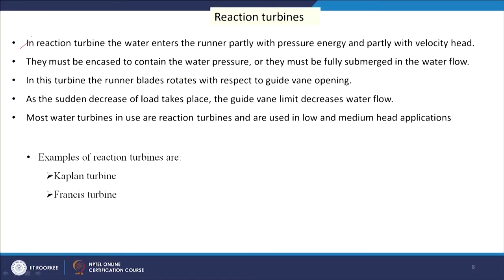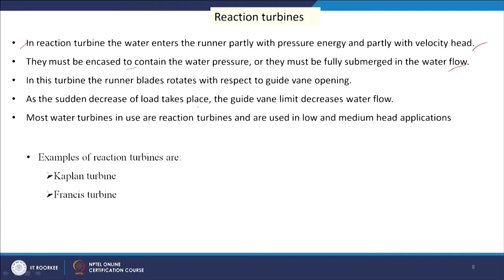In a reaction turbine, unlike an impulse turbine where water passes through nozzles and hits the blades, water enters the runner partly with pressure energy and partly with velocity head. The runner must be encased to contain the water pressure or fully submerged. Runner blades rotate with respect to guide vanes which control flow and hence blade speed. When load suddenly decreases, the guide vanes reduce water flow. Most water turbines in use are reaction turbines, used in low and medium head applications.